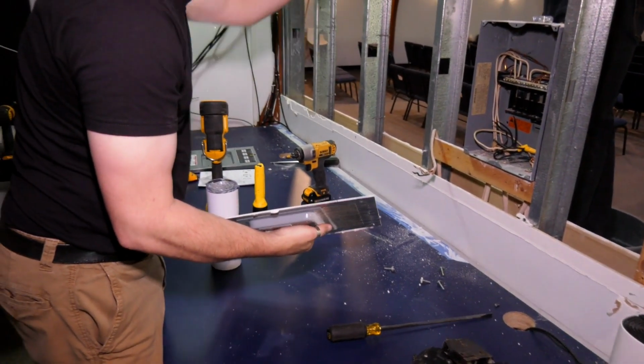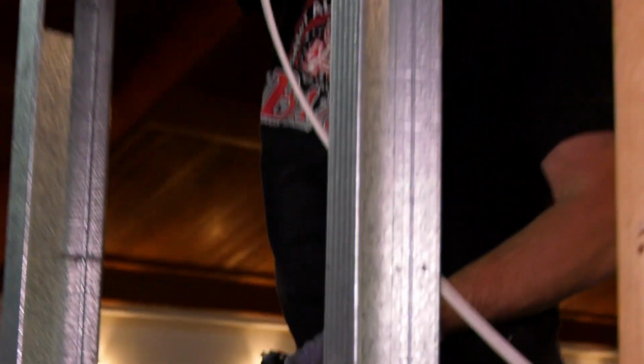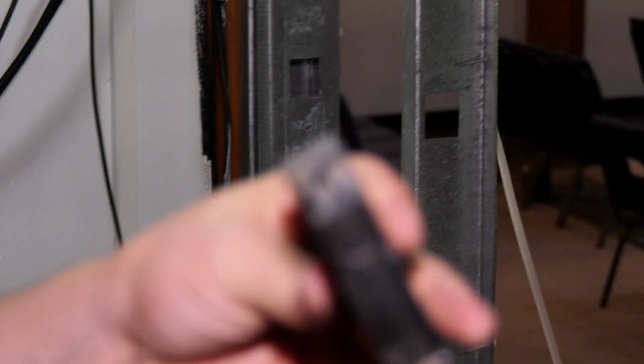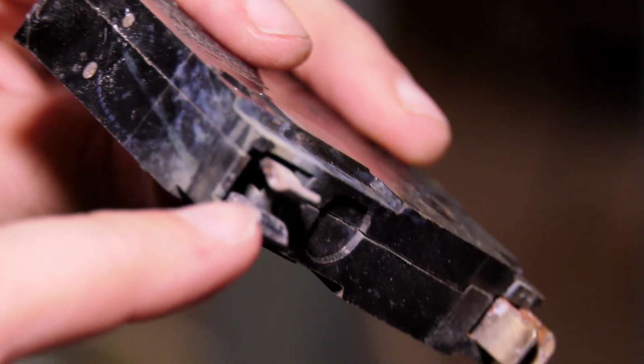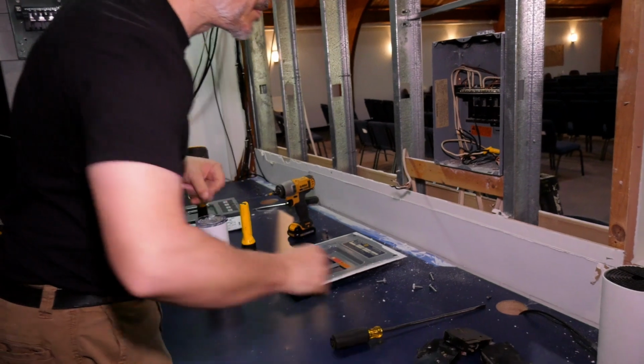Probably where it's been loose. Yep. You know what? I bet that helps. Doesn't help with our interference issue either. That constant. You see this on your breakers? That's a bad sign. Macro focus. You see right here where it's been arcing? It's just charred. It just looks really bad. It's been hot, discoloration of the plastic. But you can actually see where it's been arcing in here. So this breaker's been going bad for a while. Focus is really temperamental when I get really close.